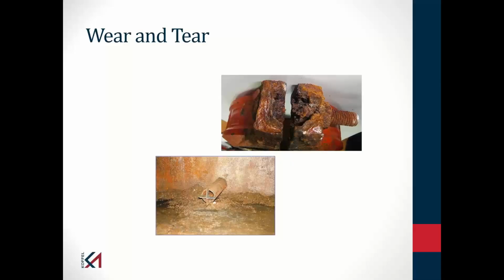during that foundation workshop. So again, the inspection activity is going to identify things like corrosion. Here we see in the lower photographs, we're doing an internal tank inspection, and we can look at the condition of the tank. And do I have silt or something accumulating in the tank that once I start flowing water through that pipe, we're going to get that into our sprinkler system. And yes, it may go through that 6-inch pipe, but it may not make its way through that 1-inch pipe that we have going to that sprinkler.